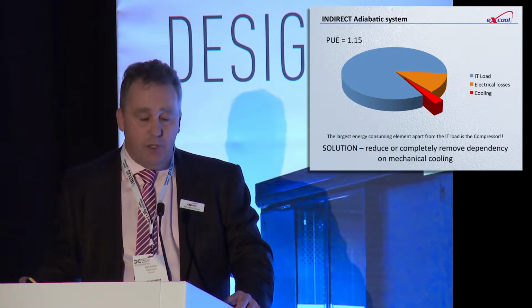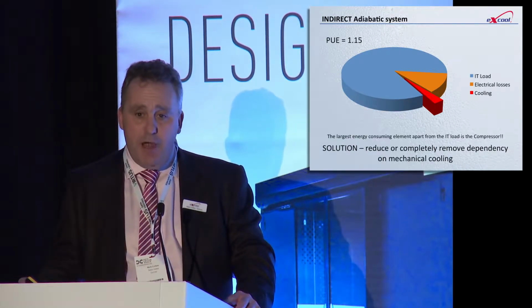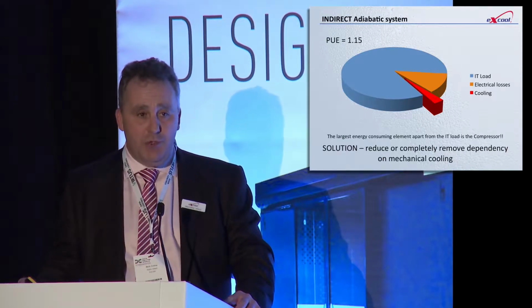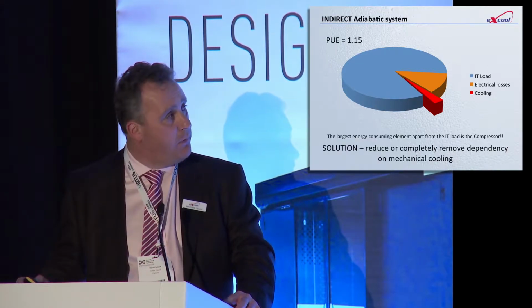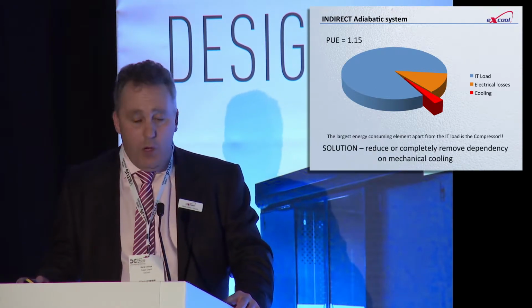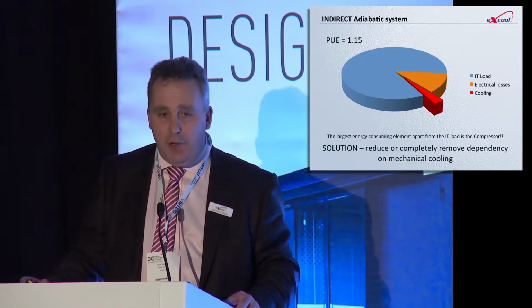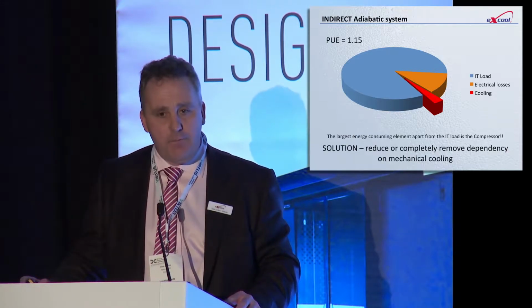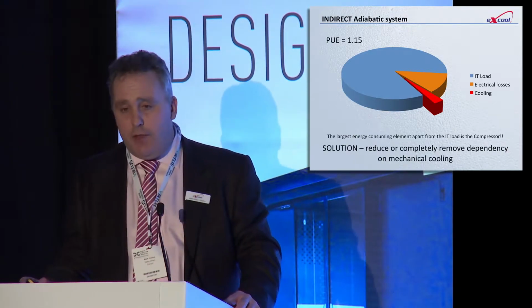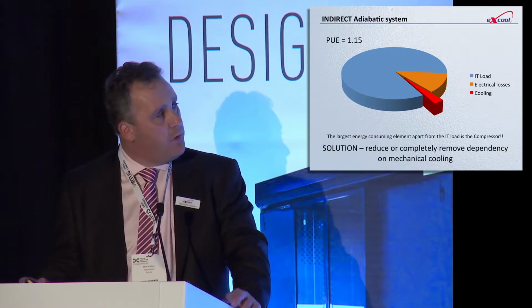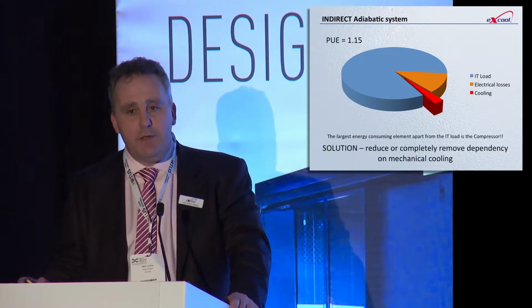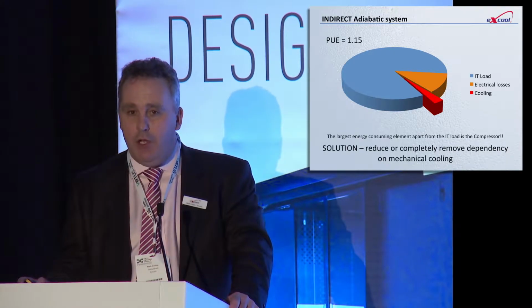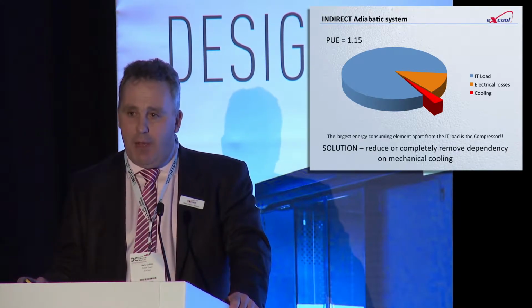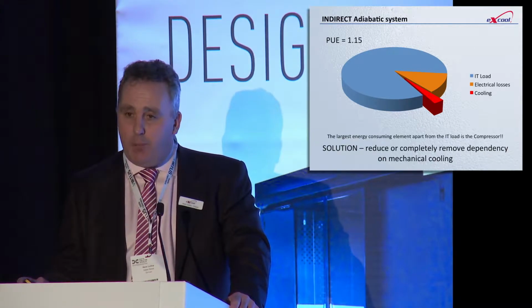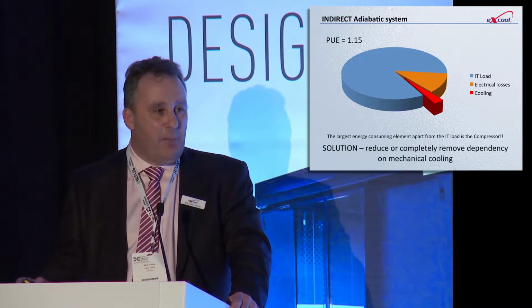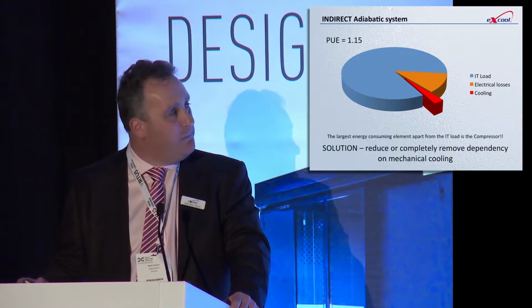As I say, the solution to reducing your PUE and increasing your reliability is to remove or reduce your dependency on mechanical cooling. Typically in the data centers that we're working on, we're seeing calculated PUEs now of 1.15. And in terms of that chart that we just put up there before for the PUE of 2, we're seeing only a small chunk of that power is required for cooling. So we're releasing that stranded power back to the operator, who can then deploy that power for what is really the purpose of the data center, and that is for IT processing.